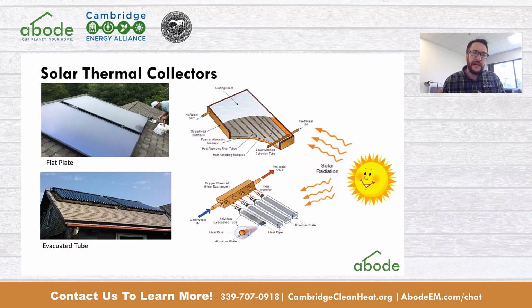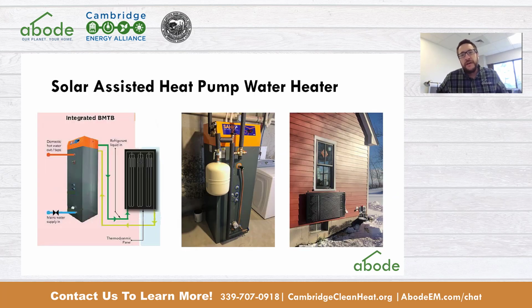There are 2 different types of collectors that are typically sold in New England. One is the flat plate. It's a little bit more seamless looking and a little bit more affordable, but does have a little bit less production. And then there are the evacuated tubes, which we're seeing at the bottom. Those are more efficient, a little bit more expensive. But if roof space is limited and you do want to produce as much solar hot water as possible, the evacuated tubes are a really good option.